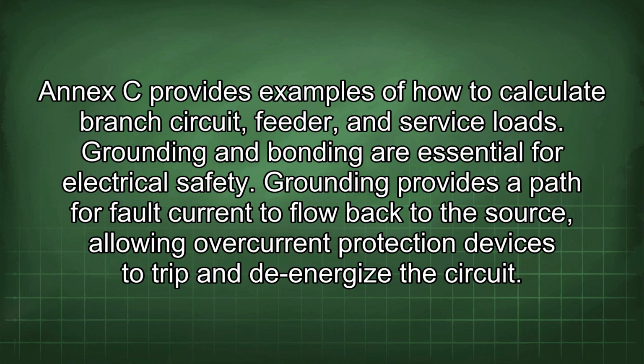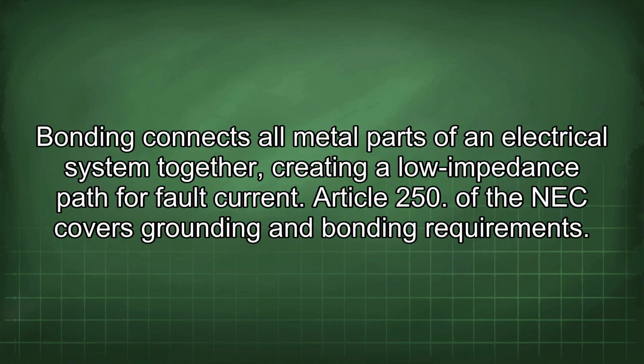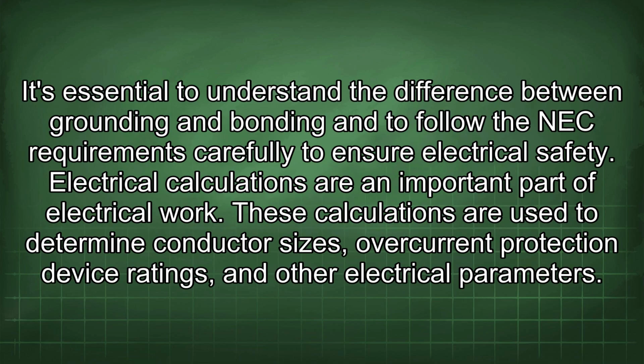Grounding and bonding are essential for electrical safety. Grounding provides a path for fault current to flow back to the source, allowing overcurrent protection devices to trip and de-energize the circuit. Bonding connects all metal parts of an electrical system together, creating a low impedance path for fault current. Article 250 of the NEC covers grounding and bonding requirements. It's essential to understand the difference between grounding and bonding and to follow the NEC requirements carefully to ensure electrical safety.